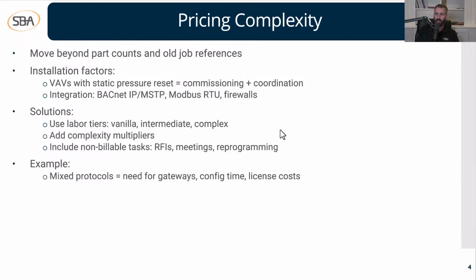So here are some installation factors, a couple of examples. Take a VAV job with static pressure reset - it's not just one controller per box. You also have to factor in labor, commissioning, graphics, startup and checkout. There could be air balance coordination, where you work with the test and balance agent, driving dampers open and closed to make sure they're getting the proper CFM and airflow. Often you'll need zone level tweaks too, maybe an offset on a zone sensor.